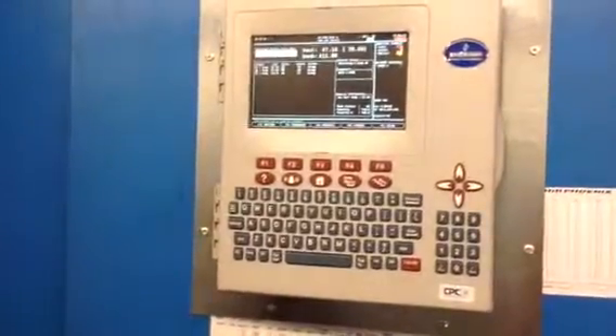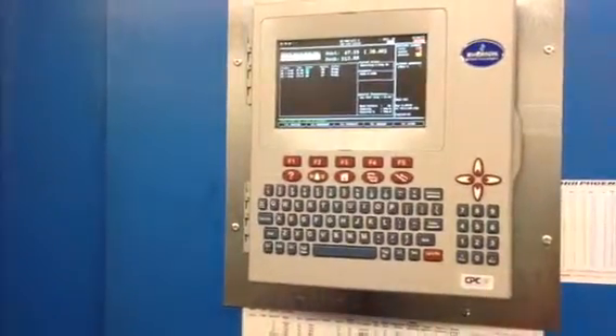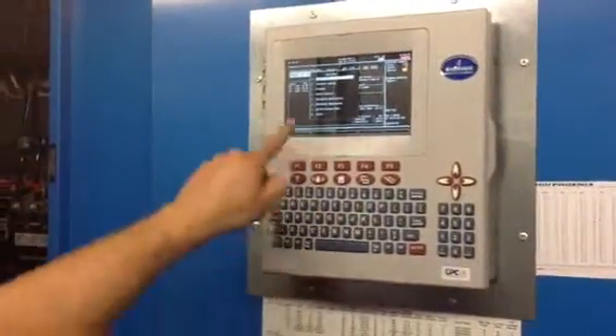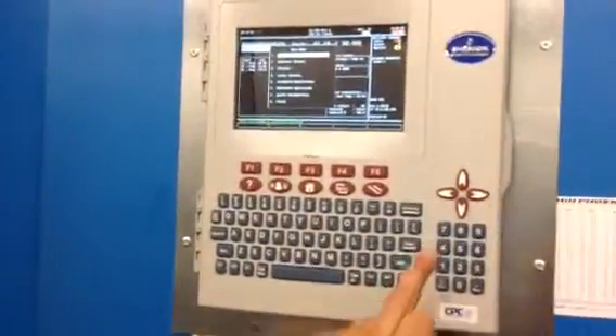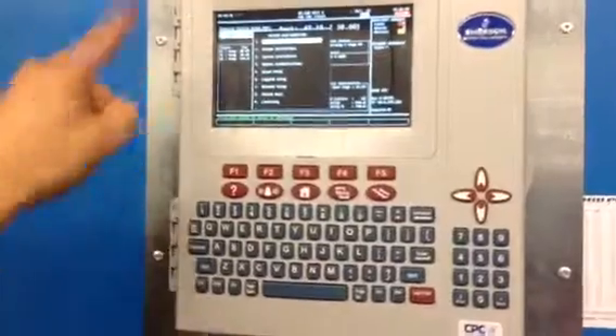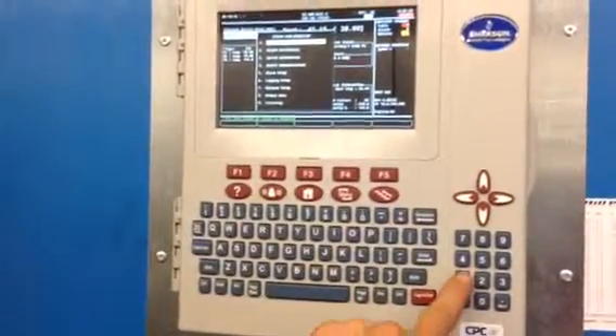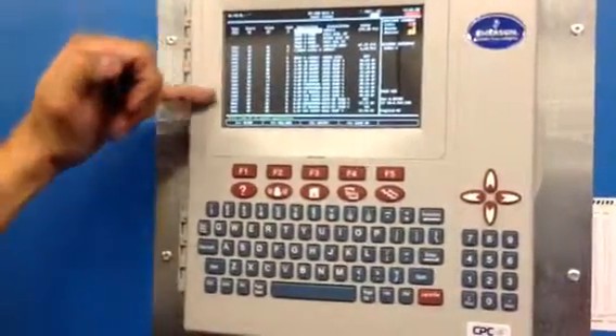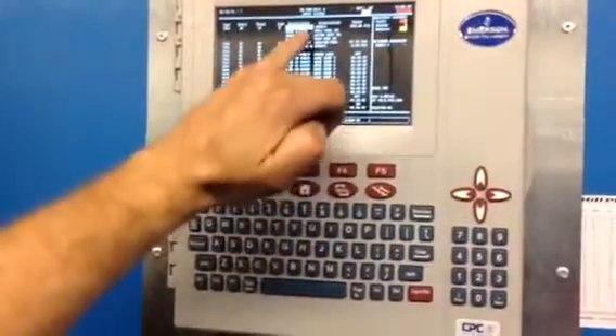Now we know we're running 50 pounds, we need to calibrate it, see what the controller's telling. 47.19, so we're off by 3 pounds. This is showing 3 pounds lower than our actual. So you want to go to Menu, System Configuration, which is number 7, then number 1, Input Definitions. Here's all your board and points, here's your associations.